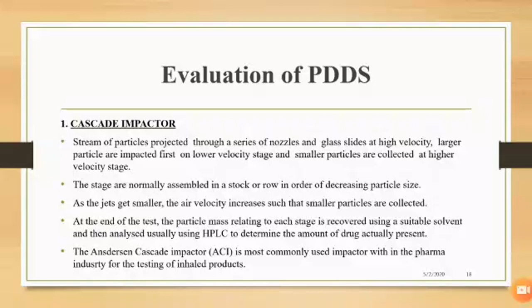A cascade impactor contains a series of stages with decreasing sieve size. So when we pump the aerosol into the nozzle, it will pass through different stages of the impactor. At low velocity, larger particles are impacted first, and at high velocity, smaller particles are collected. At the end, the particles at each stage are recovered with the help of a suitable solvent and analyzed using HPLC to determine the amount of drug actually present. The Andersen cascade impactor is the most commonly used impactor in the pharma industry for the testing of inhaled products.